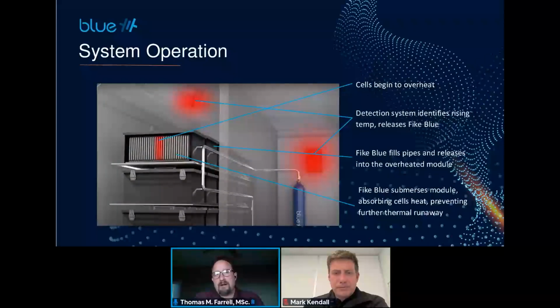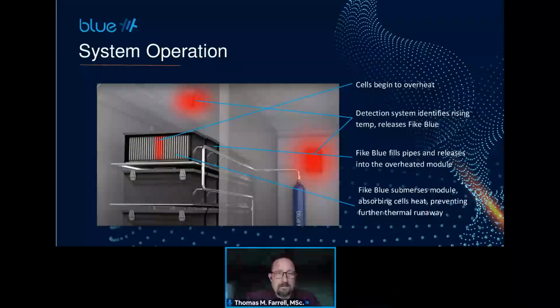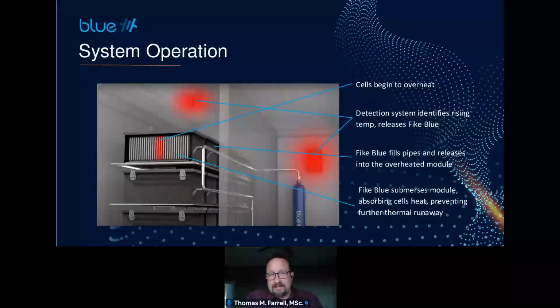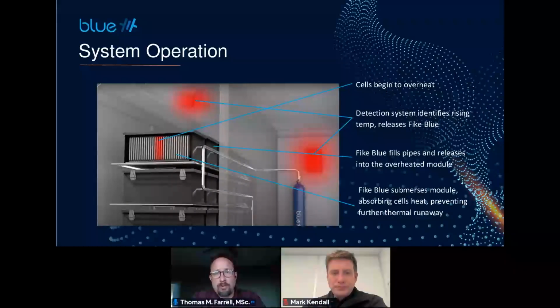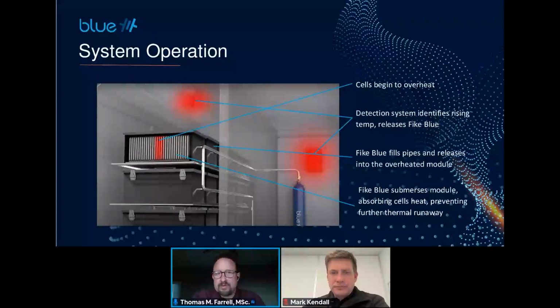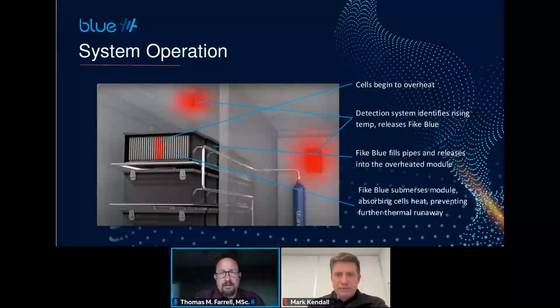When a cell begins to overheat, there are a number of ways that can be detected. That can be onboard gas detection inside the module itself. Depending on the battery type, it could be detection somewhere else in the room. If you have a UL-rated BMS, that could be used as part of the protective system. When that is detected, the control valve on the main tank opens and floods the network that goes to all those modules. Depending on the system and design, you can have a total flood of everything in your rack, or a localized flood of the module undergoing thermal runaway, to directly target that threat at its point of origin. That can be done a number of different ways, with both passive and active actuation techniques.